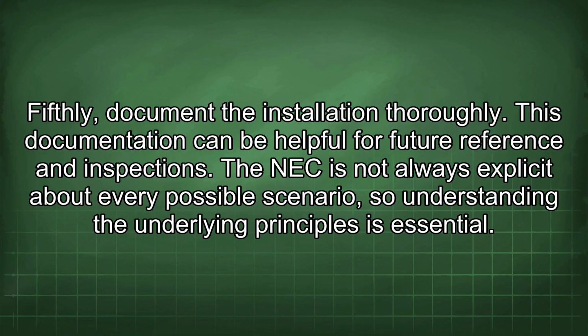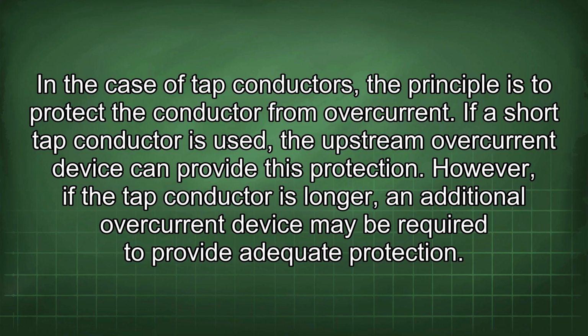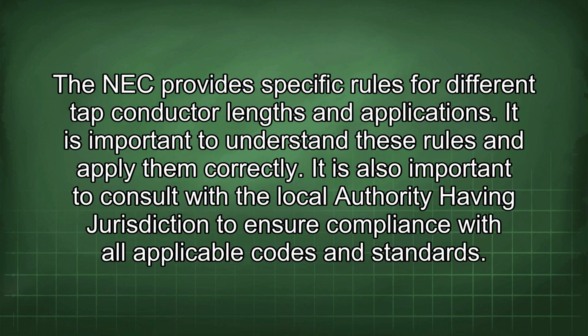The NEC is not always explicit about every possible scenario, so understanding the underlying principles is essential. In the case of tap conductors, the principle is to protect the conductor from overcurrent. If a short tap conductor is used, the upstream overcurrent device can provide this protection. However, if the tap conductor is longer, an additional overcurrent device may be required to provide adequate protection. The NEC provides specific rules for different tap conductor lengths and applications. It is important to understand these rules and apply them correctly.